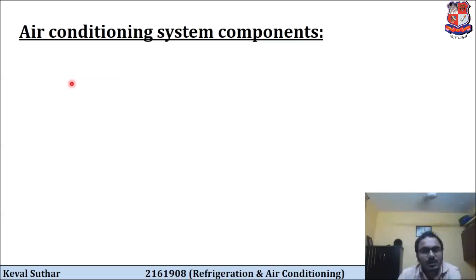So now we will discuss about air conditioning system components. First is cooling source. The equipment that removes the heat is called cooling system. It has compressor or generator and absorber. If it is compressor, then it should be VCR, and instead of compressor, if we are having generator and absorber, then it will be VAR system. So this cooling source has compressor or generator and absorber, and then evaporator, condenser and expansion device. So these are all 4 basic components of our refrigeration system.